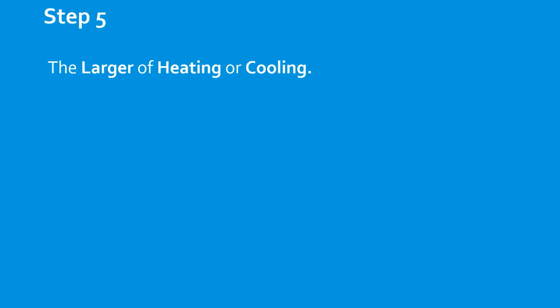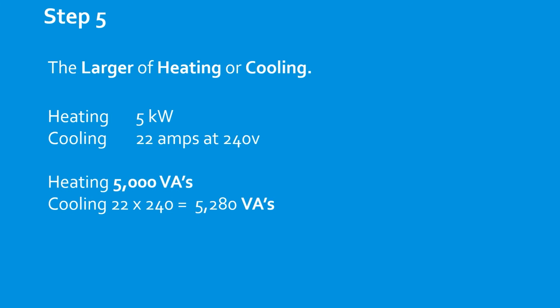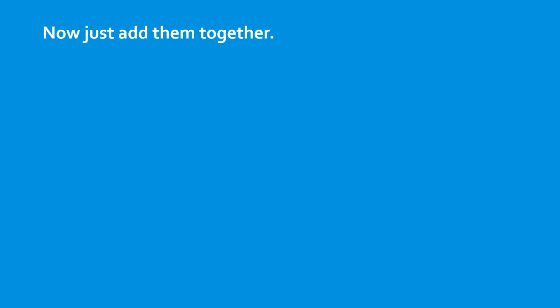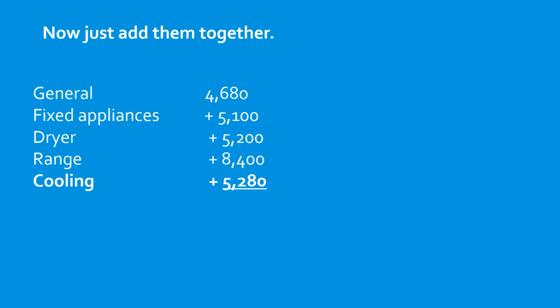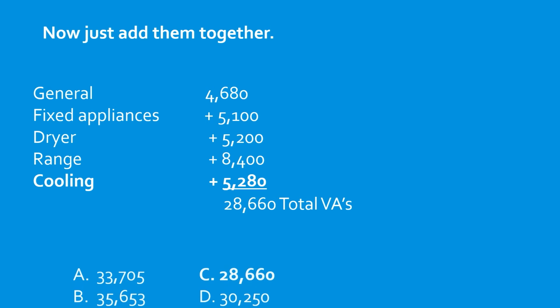Now we select the larger of the heating or cooling. Heating is 5 kW, cooling is 22 amps at 240 volts. So we are going to select the larger. In this case, it is the cooling. We just used Ohm's law and multiplied 22 by the system voltage, which is 240, and that's going to give us 5,280 VAs. Now we just add them all together. It's going to give us 28,660 total VAs for this home. And we're going to select C.